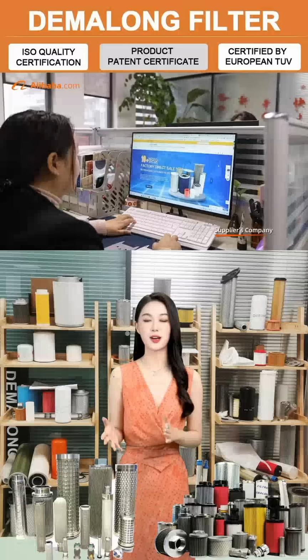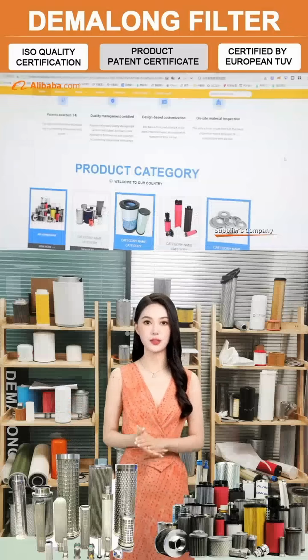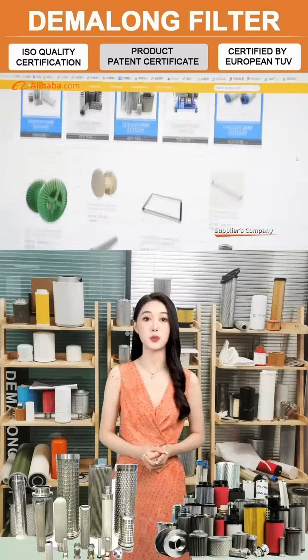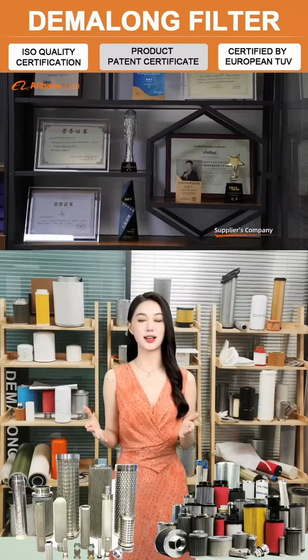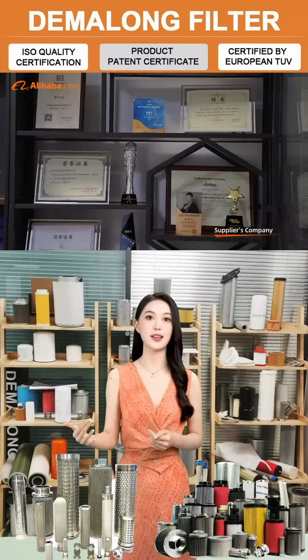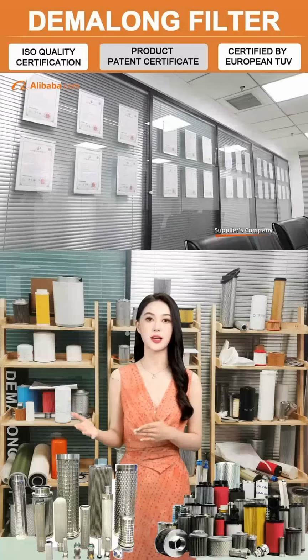The red one, the filter rating is 0.01 micron, the main function is to remove the oil mist. This green one is the active carbon element and it can remove hydrocarbons and odor.